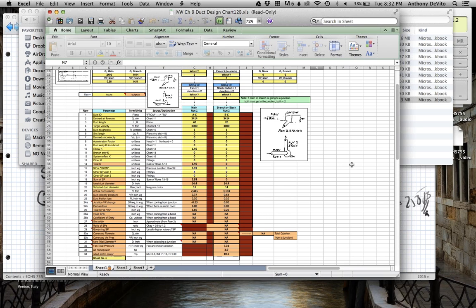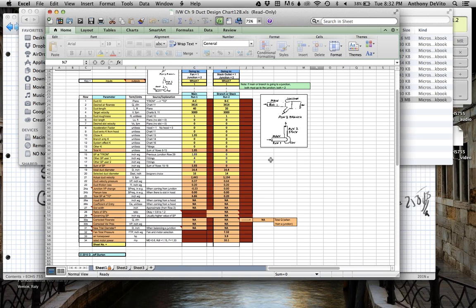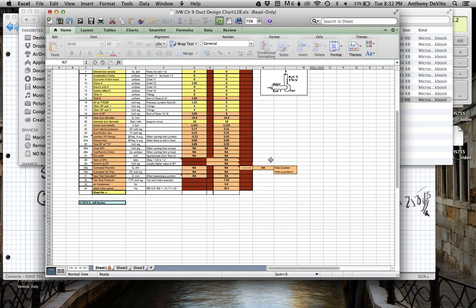Yeah. Initially, I was doing 300, but too much. Well, think about it, 300 feet per minute. Convert 300 feet per minute to miles per hour, and then think about how fast that is. If you're trying to work on something delicate, you also don't want that. You have to make a judgment as to how you have to work practically too. 100 feet per minute, 200 feet per minute, I don't think you'd feel it. You'd feel it, but I don't think it would interfere with most kinds of work that you might be doing.